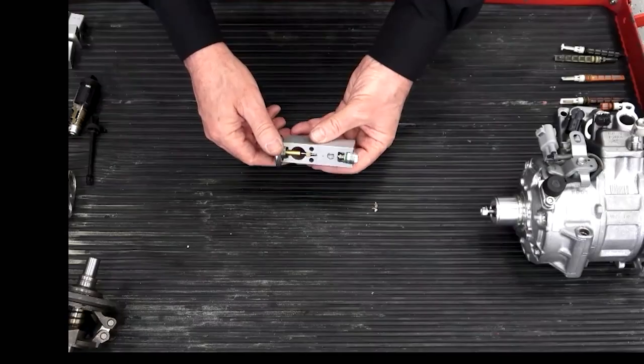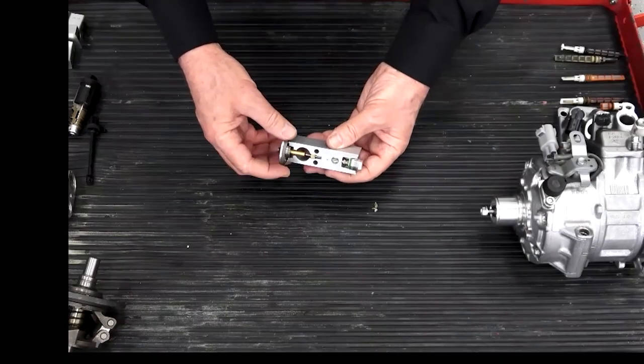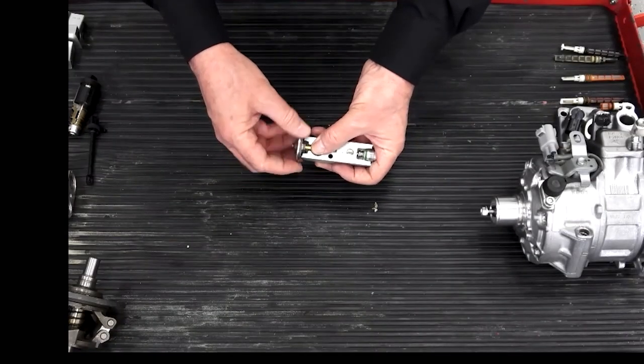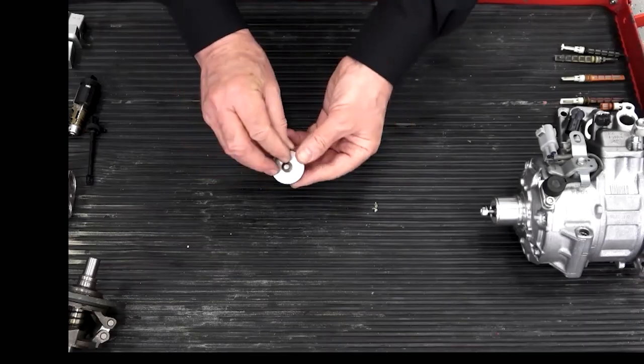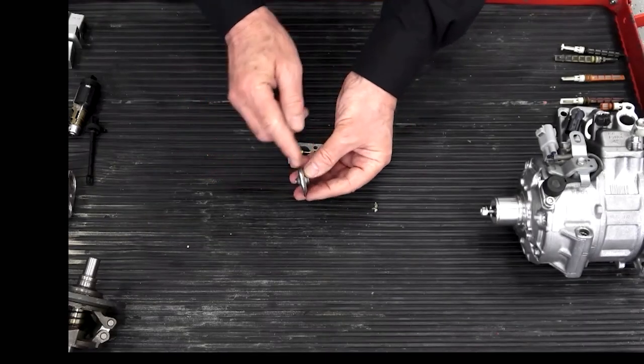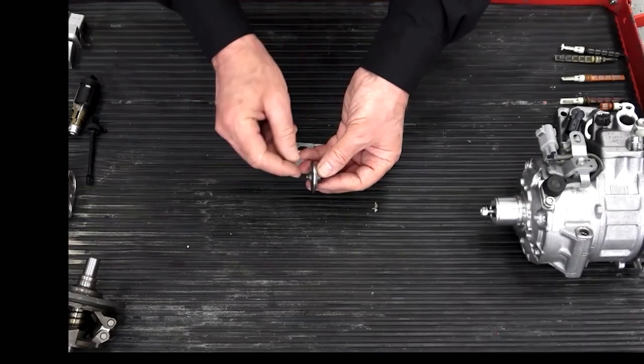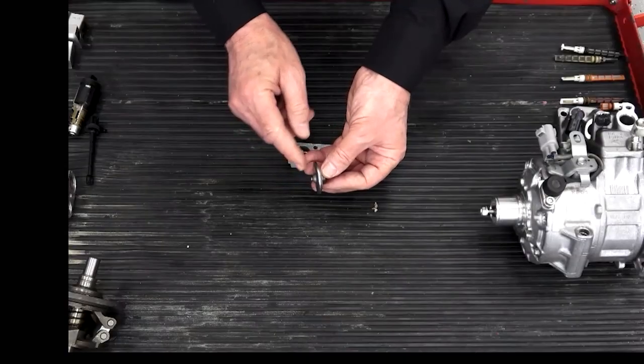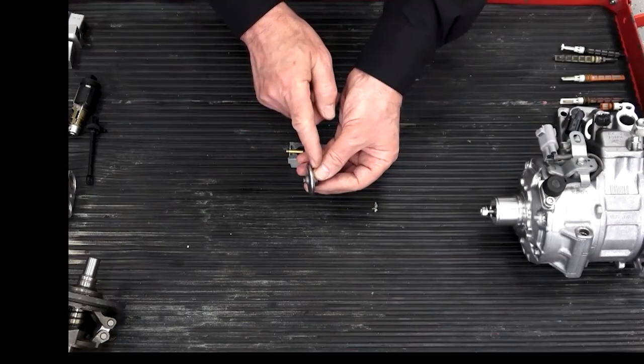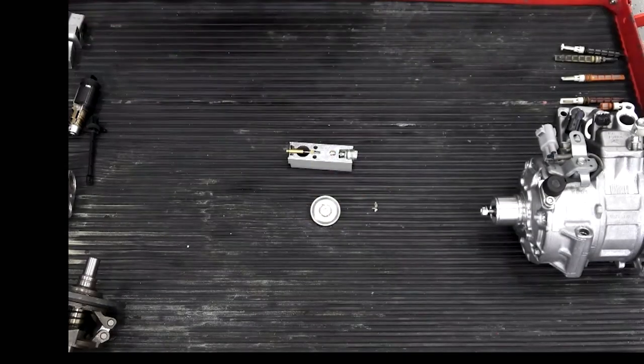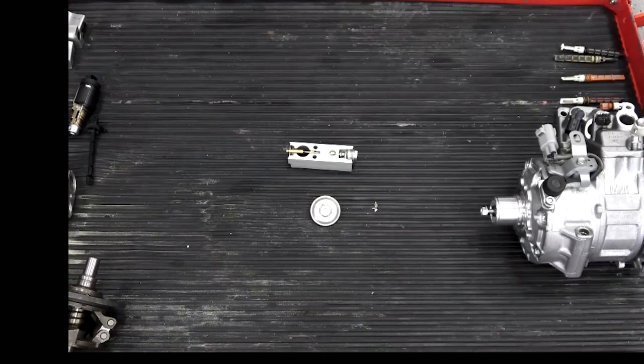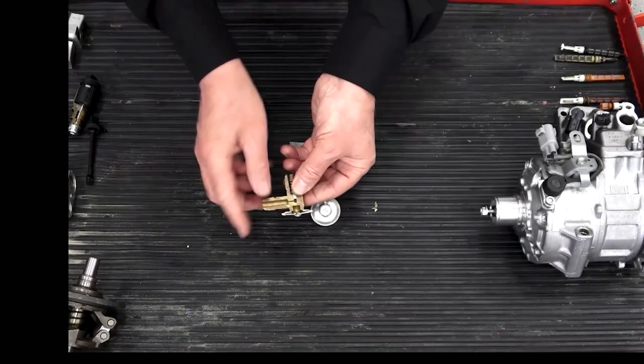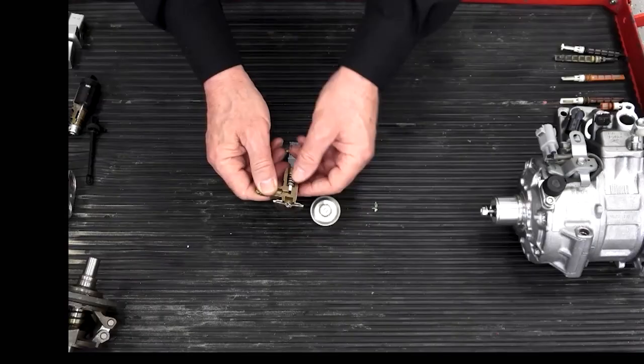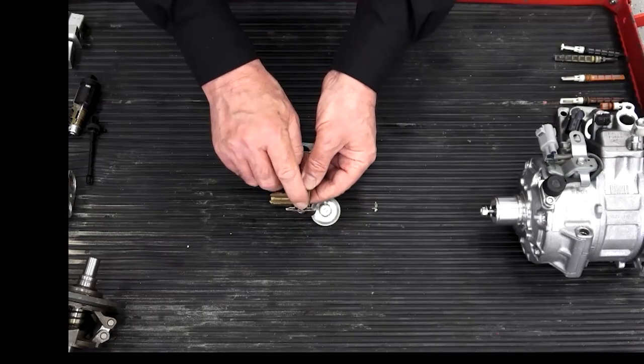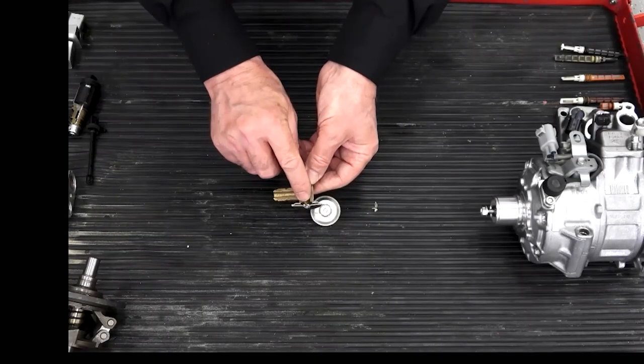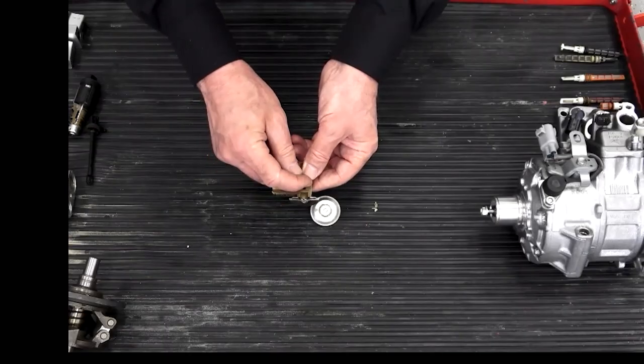And here's how a TXV valve works. This piece here, which will unscrew from any valve, we call the power element, right? It's got a stainless steel diaphragm. Think of the top of a bean can that separates the top from the bottom of the valve. In fact, I've got an older one cut apart here. You might be able to see if you look here. This is an old school valve, but the power valve is the same inside. There's a thin metal diaphragm separating the top of the valve from the underneath.